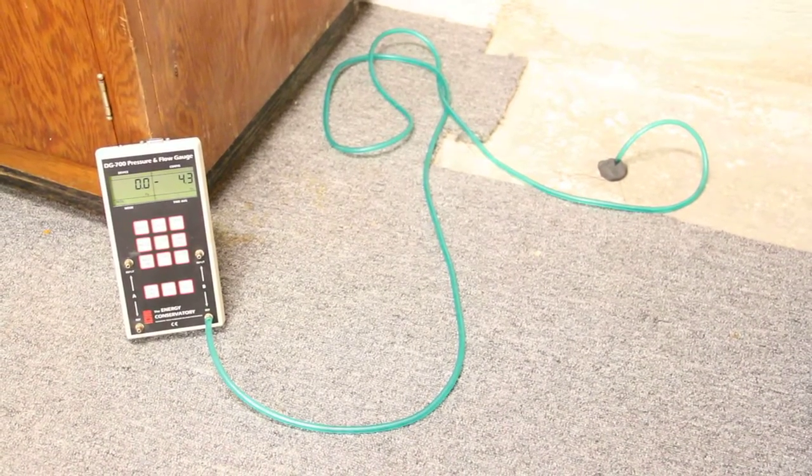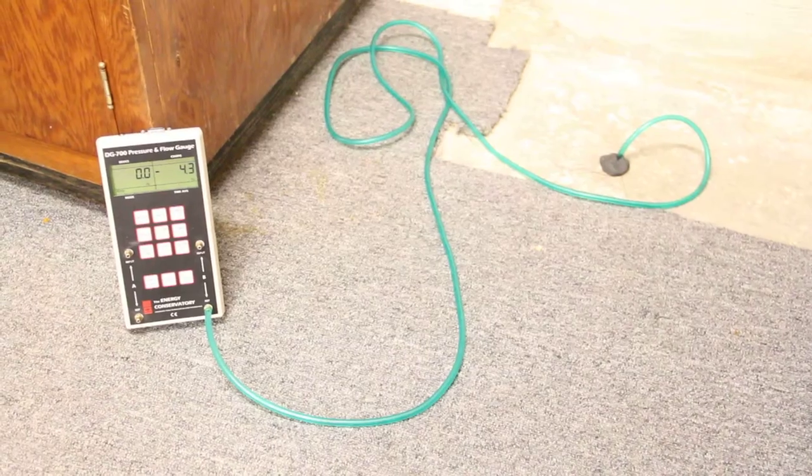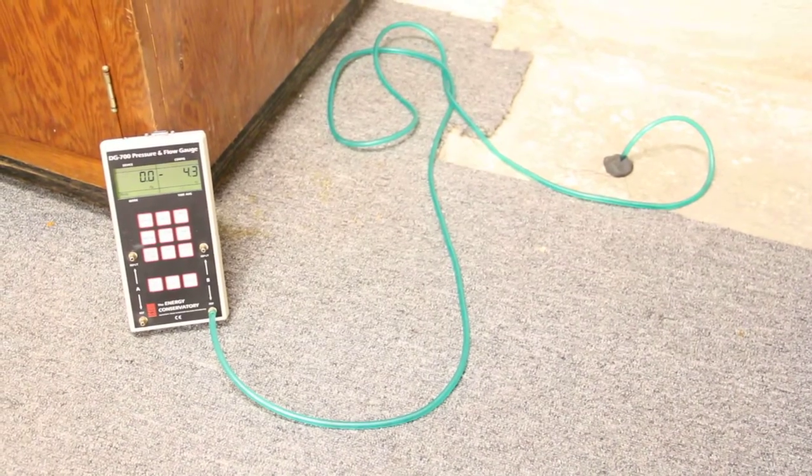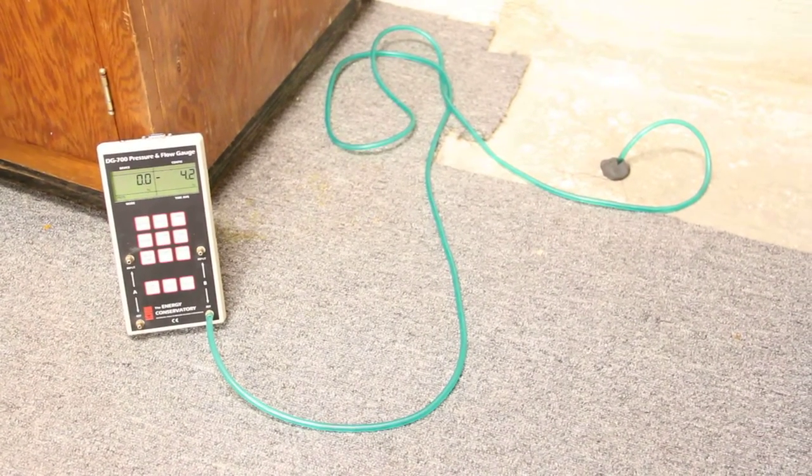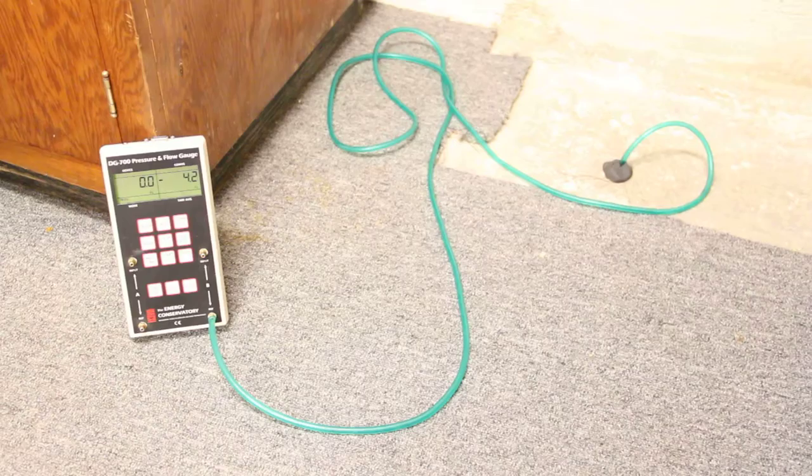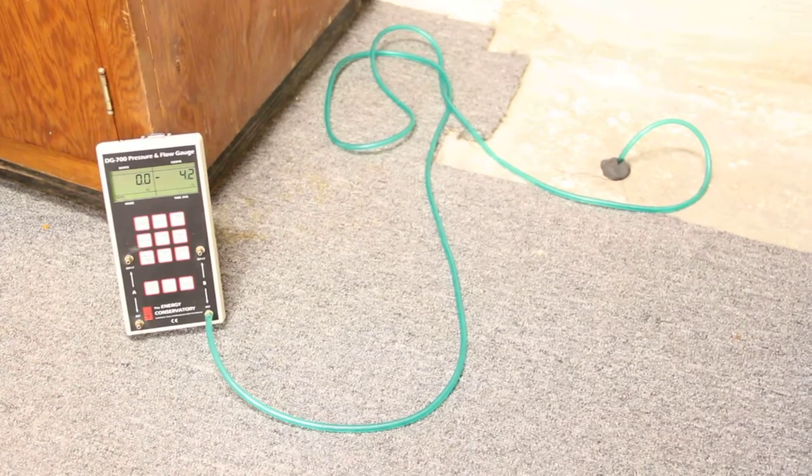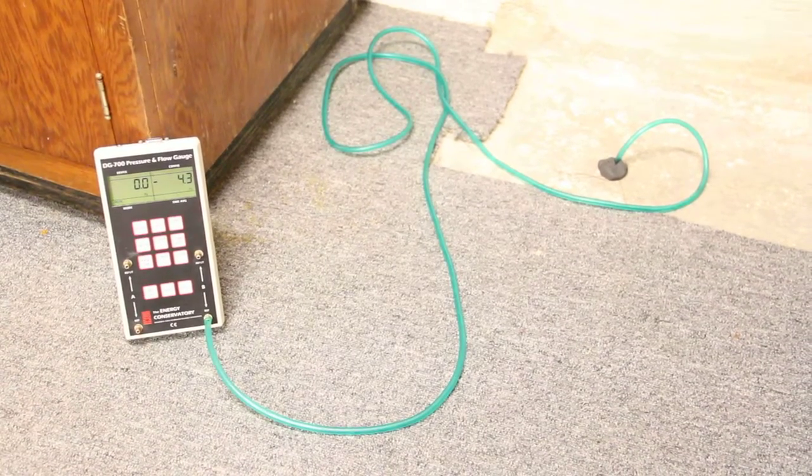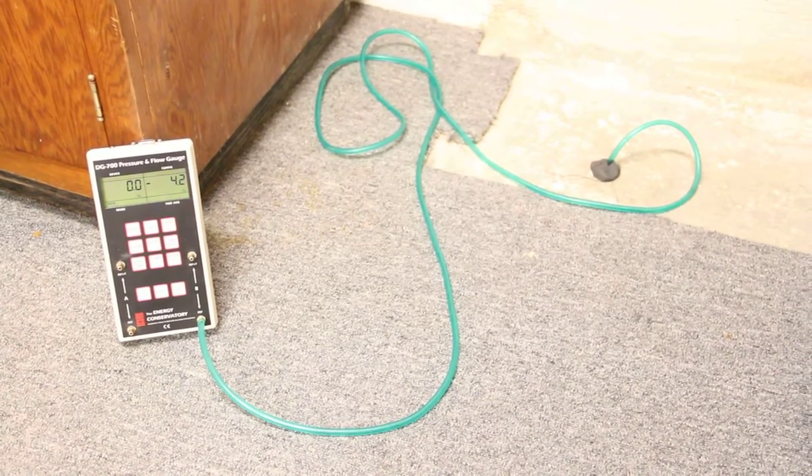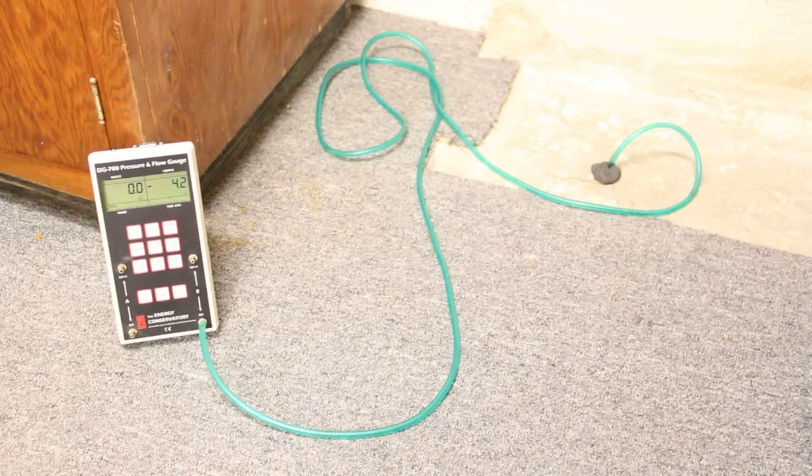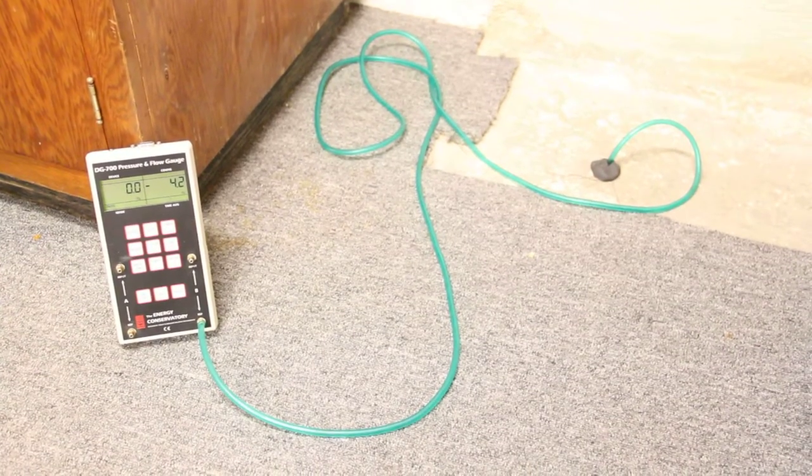Underneath the floor by a footing, and so we're showing here minus 4.3 pascals in the basement relative to the subfloor, meaning that there'd be a flow of air from the subfloor to the basement. And so we've got a test suction point set up.